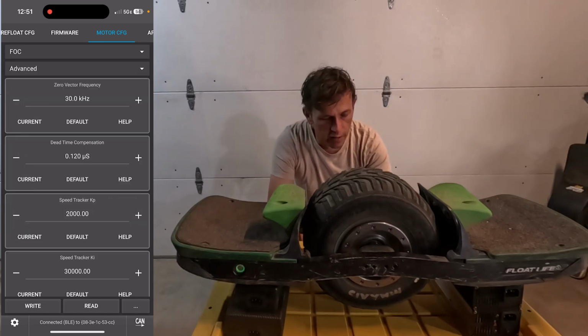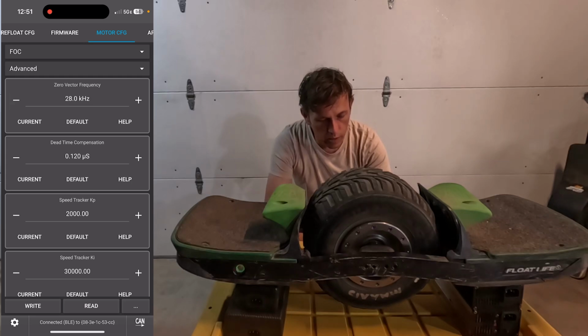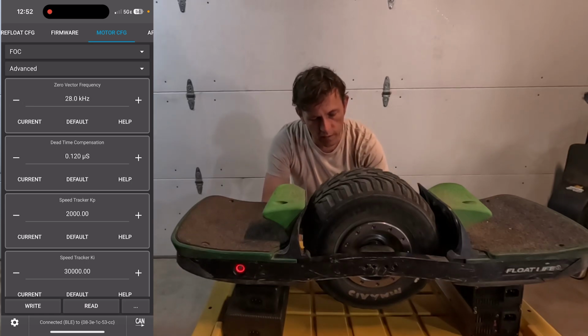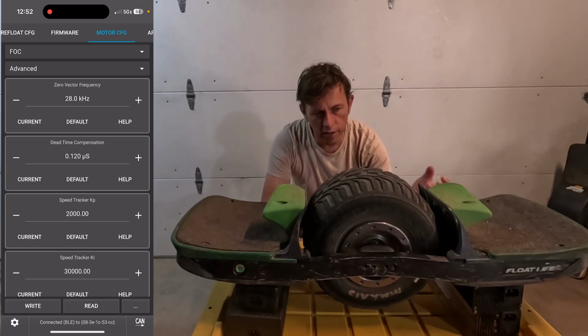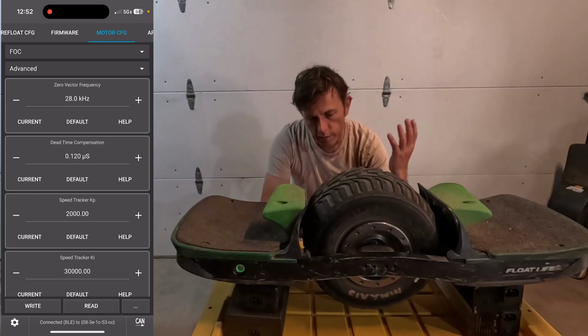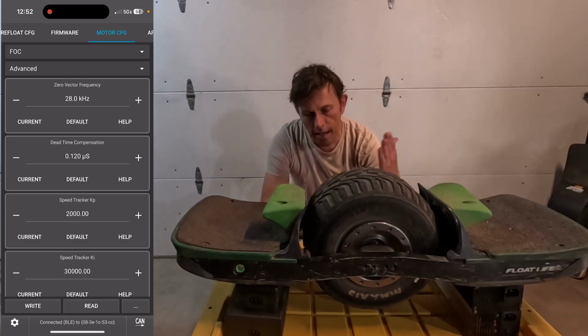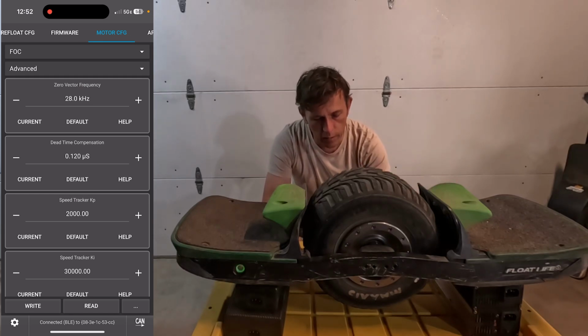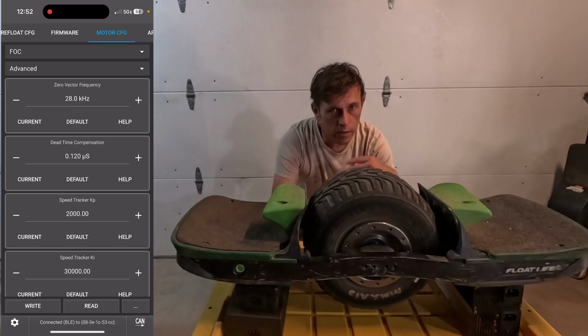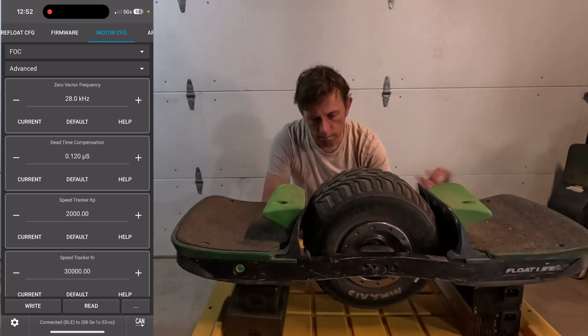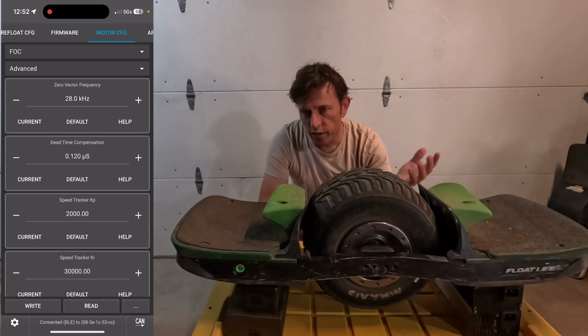So we have this zero vector frequency. This is the one that you want to tune. We used to only go up and down by 1 kilohertz here, but the way you want to go about it: changing this frequency changes the sound of the controller, it will make a noise at about half that frequency. So the lower this is, the more likely you are to hear it, and it'll be anywhere between noticeable to unpleasant and annoying.